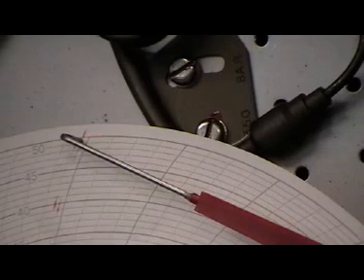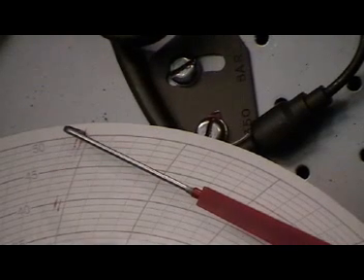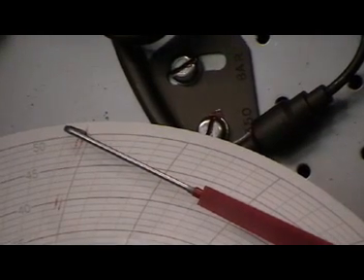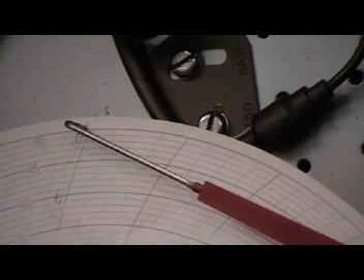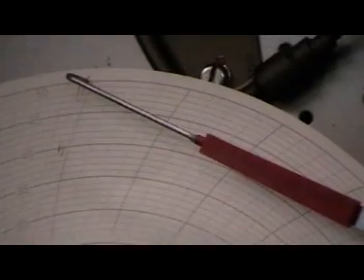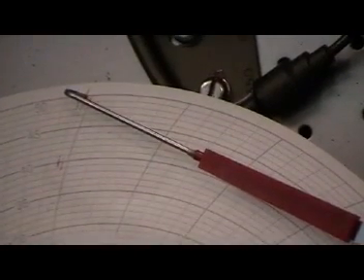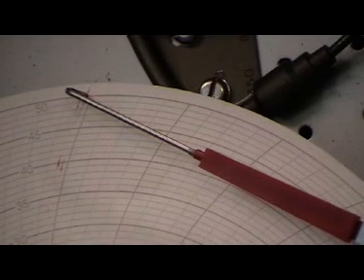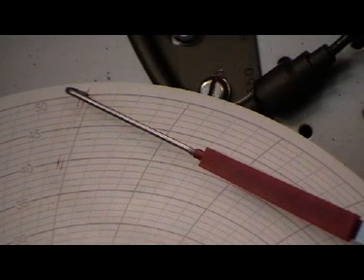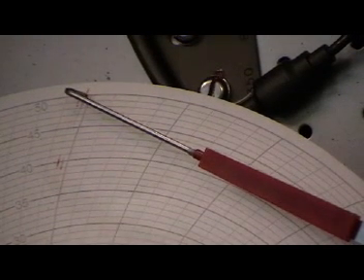Finally, as a check, you obviously should do a downscale test. 5,000, 4,000, 2,500, 1,000, 0. And the readings should be within 1% of the upscale readings, otherwise the hysteresis, as it's called, is unacceptable.